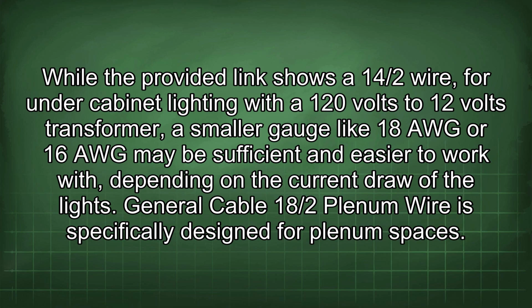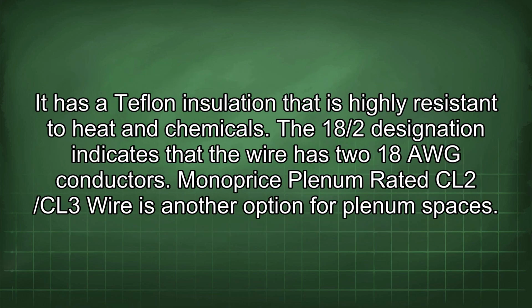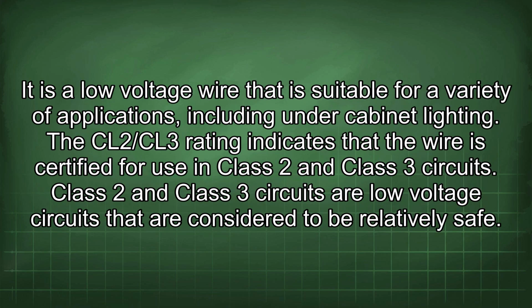General Cable 18/2 plenum wire is specifically designed for plenum spaces. It has a Teflon insulation that is highly resistant to heat and chemicals. The 18/2 designation indicates that the wire has two 18 AWG conductors. Monoprice plenum rated CL2/CL3 wire is another option for plenum spaces. It is a low-voltage wire that is suitable for a variety of applications, including under-cabinet lighting. The CL2/CL3 rating indicates that the wire is certified for use in Class 2 and Class 3 circuits.